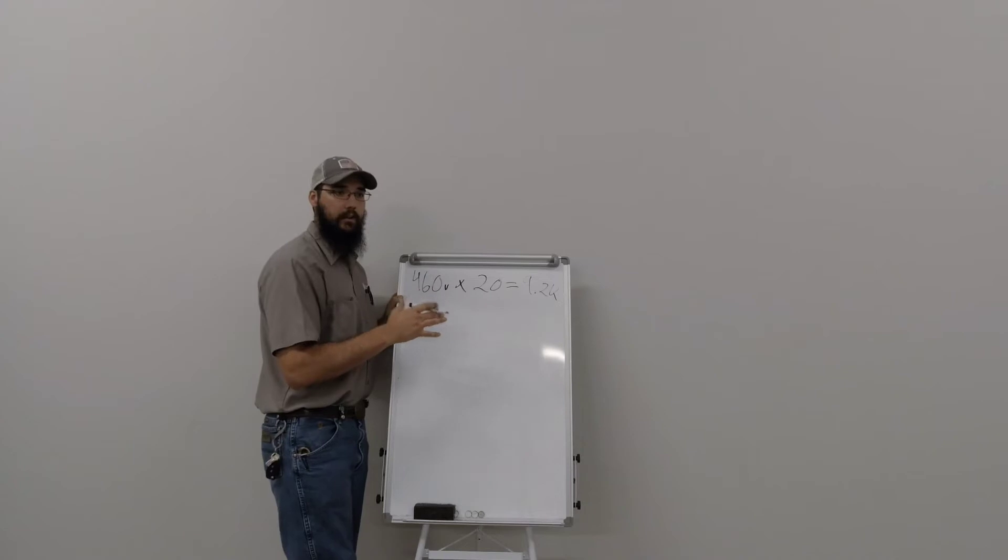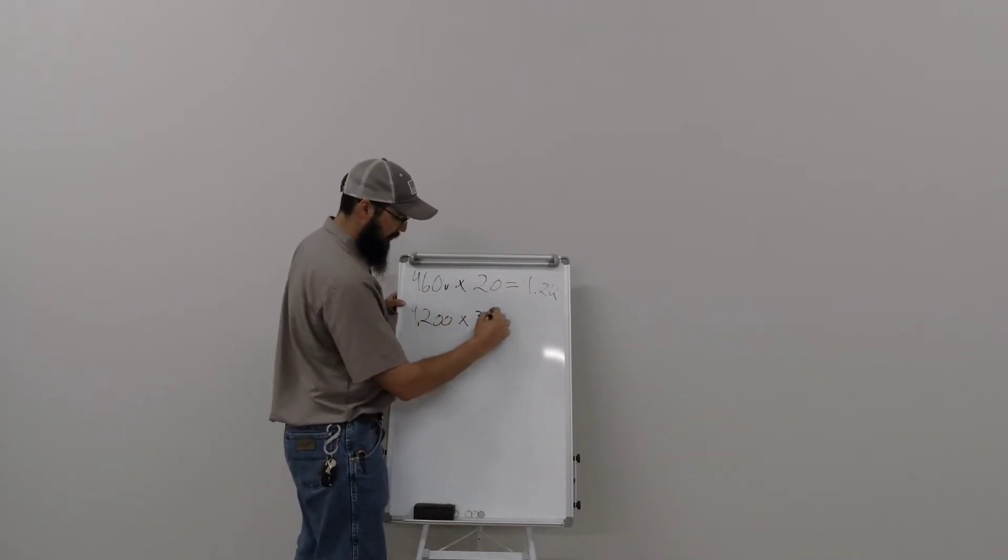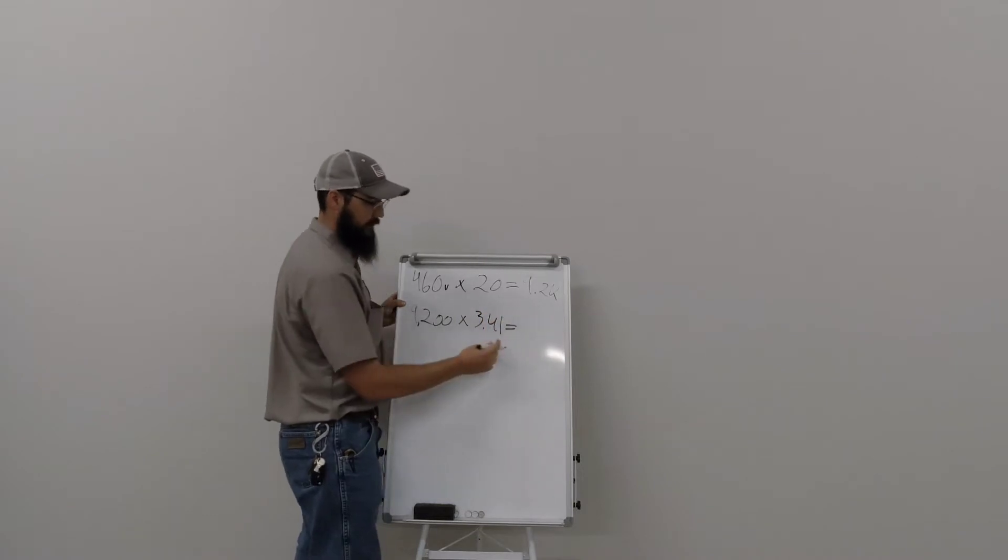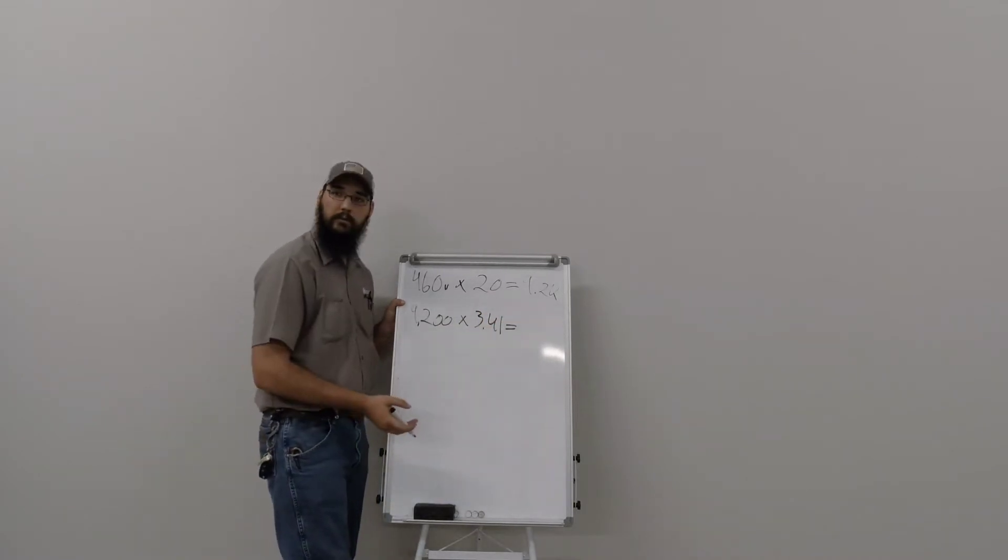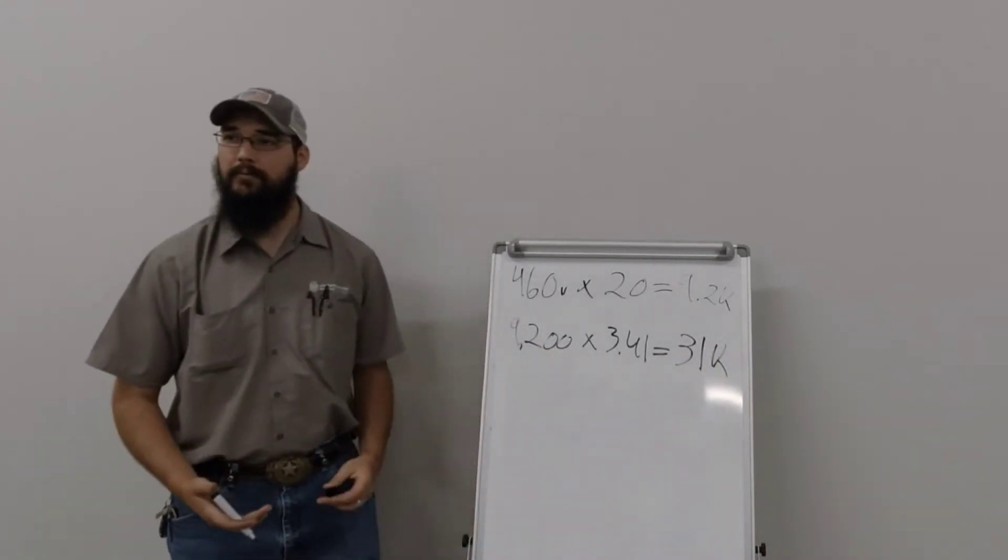That's your watts. So we have 9200 watts. So 9200 times 3.41 watts conversion gives you how many BTUs? So 31,000 BTUs. So 31,000 BTUs at the end of the day. Right?